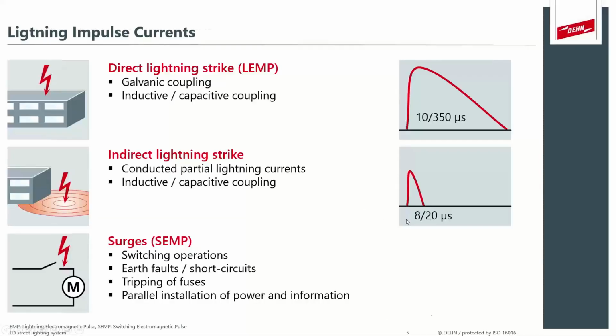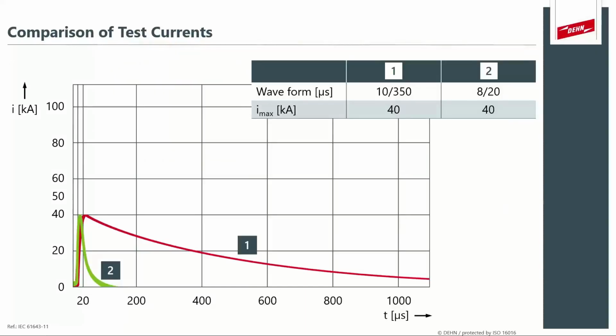Now, to overlay the two wave shapes and show you the difference, you can see the red curve being the 10 by 350 microsecond and the green curve being the 8 by 20. So the red is the direct lightning strike and the green wave shape is a surge or an indirect lightning strike. Both of these strikes actually peak at 40 kiloamps. So that means that we don't characterize the peak as the main factor for calculating damage based on surge or lightning strikes. It's all dependent on the wave shape.